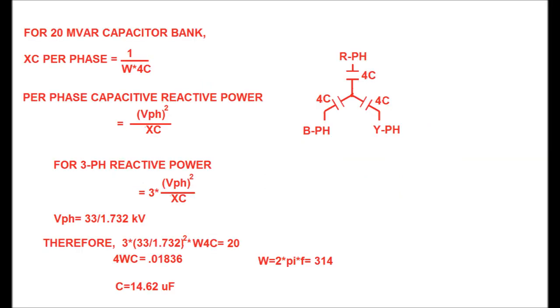The rating of the capacitor bank is 20 MVAR. The capacitive reactance per phase is XC = 1 / (ω × 4C), since the equivalent capacitance per phase is 4C. The per-phase capacitive reactive power is equal to V_phase² / XC.